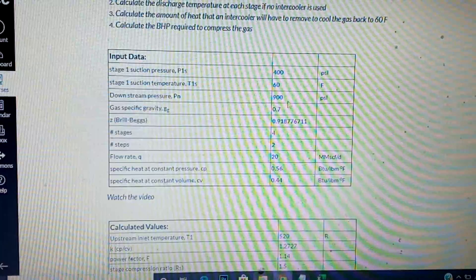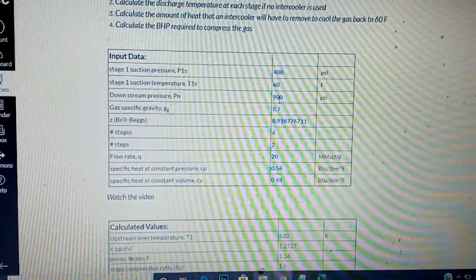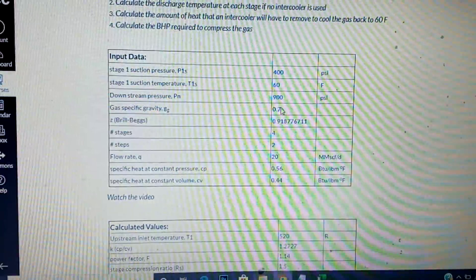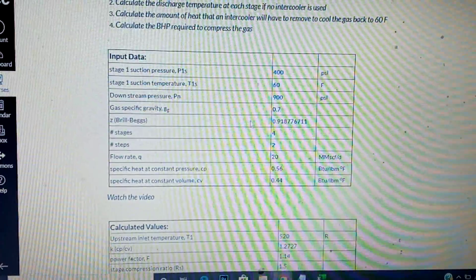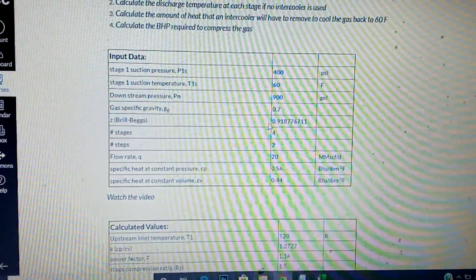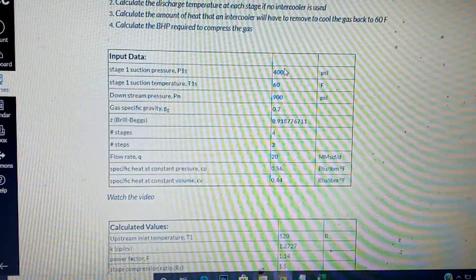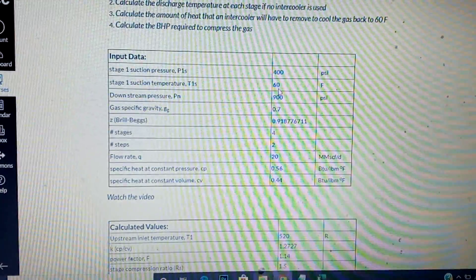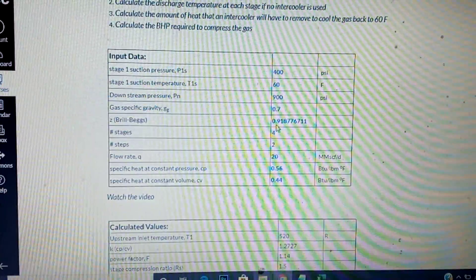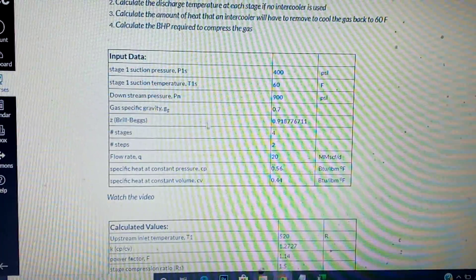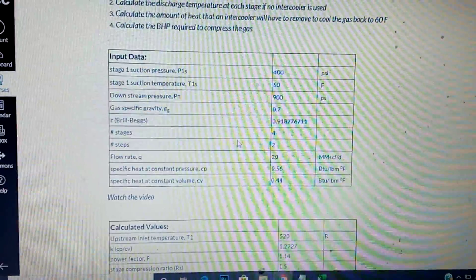The downstream pressure is the pressure at any given stage — you need that to calculate the stage compression ratio. We're going to use Brill-Beggs to find Z. You input the inlet pressure of 400, the temperature of 60, and the specific gravity of 0.7, with mole fraction set to 0. That gives you the Z value.